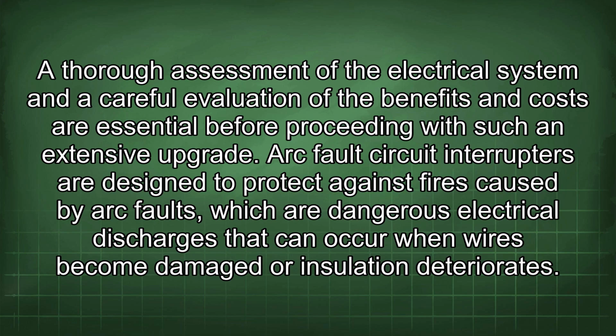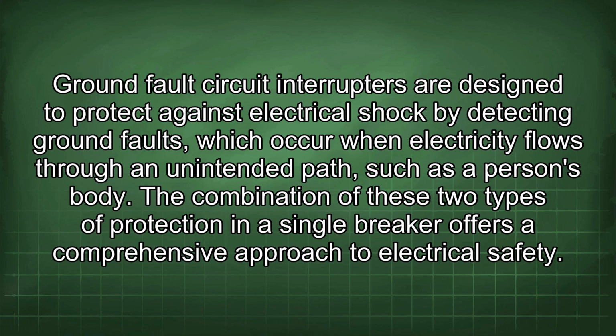Arc fault circuit interrupters are designed to protect against fires caused by arc fault, which are dangerous electrical discharges that can occur when wires become damaged or insulation deteriorates. Ground fault circuit interrupters are designed to protect against electrical shock by detecting ground faults, which occur when electricity flows through an unintended path, such as a person's body. The combination of these two types of protection in a single breaker offers a comprehensive approach to electrical safety.